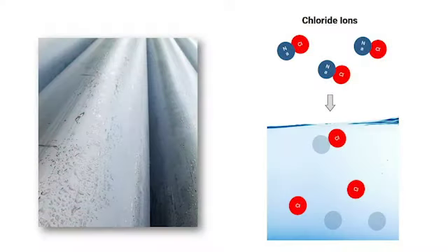Correct. However, chloride ions from many salts that are dissolved into water can strip away this chromium oxide layer. These chloride ions could be introduced to the system from a number of sources, including rainfall, scheduled washdowns of piping and equipment, and they can even leach into water already present in the system from the insulation material itself. For this reason, the chemical composition of materials used with austenitic stainless steel becomes an important consideration.